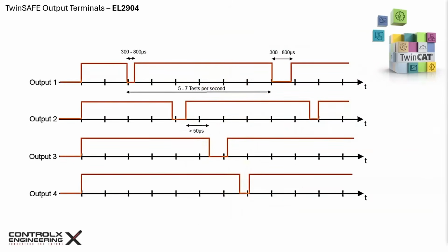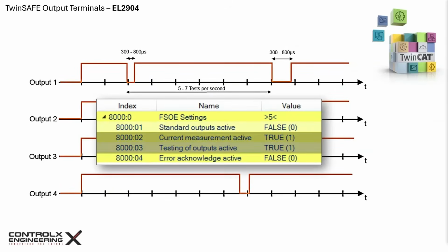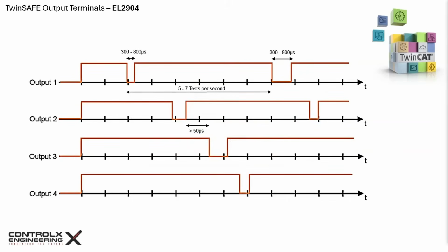Like the EL1904 safety input terminal, the EL2904 also uses test pulses and output channel testing, as I mentioned earlier. This diagram shows a typical test pulse chart for the 4 outputs. The parameters current measuring active and testing of outputs active should be enabled in TwinSAFE. The EL2904 briefly injects control test pulses into the output circuits to verify that the output transistor can switch correctly, the wiring to the actuator is intact, no external fault is present, and that the measured current matches the expected behavior. This is part of the terminal's fail-safe design. If the tests detect anything abnormal, the EL2904 will immediately switch the affected channel to a safe state.